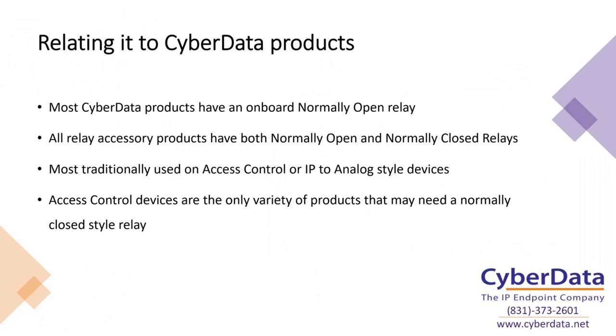If you need a normally closed style relay, or you're dealing with a higher voltage, higher amperage situation — say a gate controller instead of a regular door strike — those are the instances where you might need one of our accessory products. Definitely work with our team if you're not sure. When dealing with all of our different products that have onboard relays, you're really not going to need a normally closed style relay for IP-to-analog or with our speakers that also have an onboard relay. Those are always going to be a normally open, temporarily closed style — I've never encountered a system that needs normally closed there. So those are traditionally regulated to the access control segment.